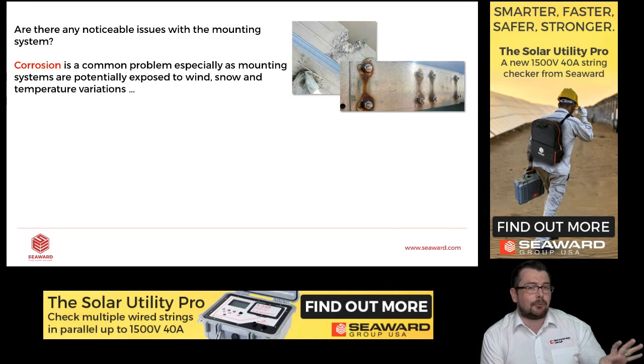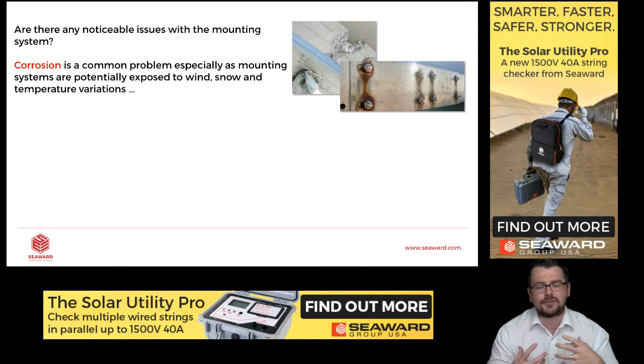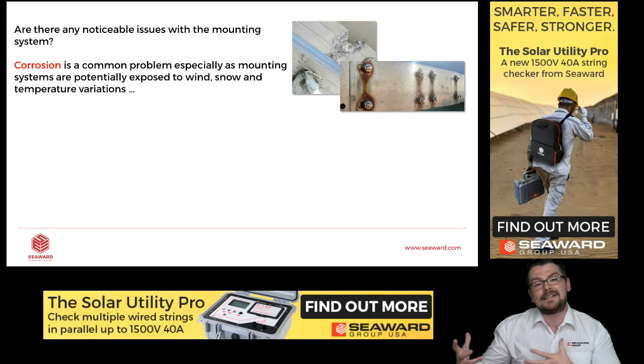Corrosion is a very big problem, particularly if we're in a high saline environment, say by the ocean. The salt in the atmosphere can really degrade aluminum systems, particularly if the layer of anodization has been corrupted or wasn't applied correctly to the metal itself.